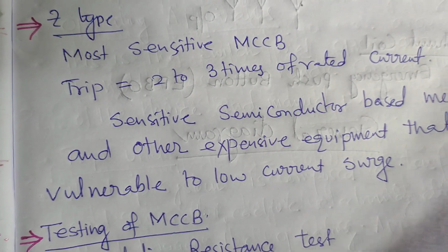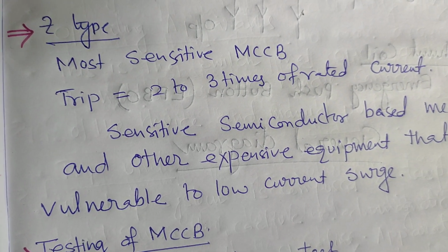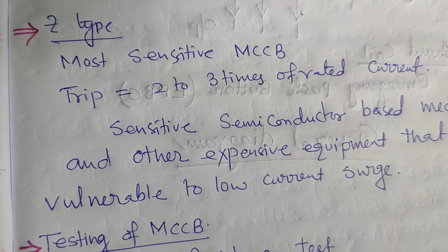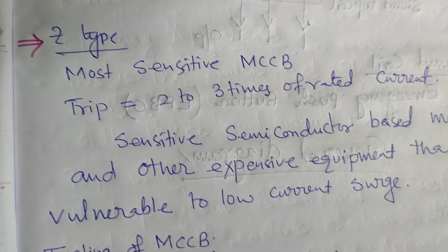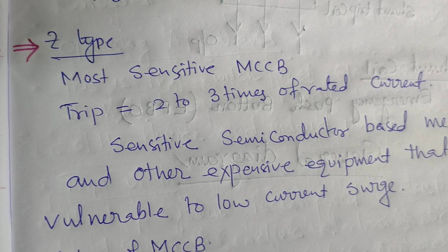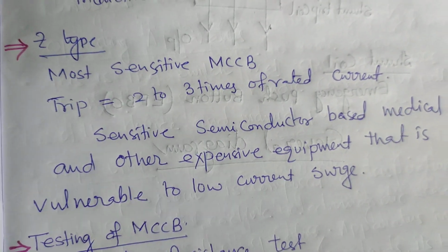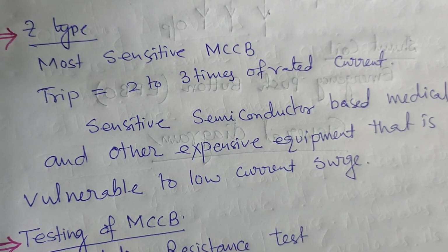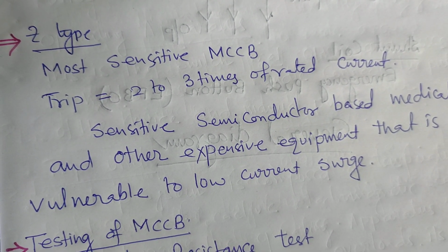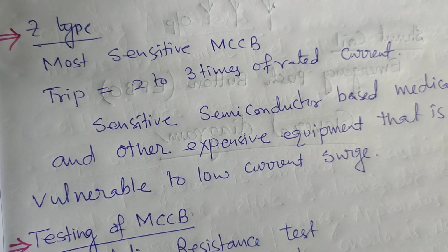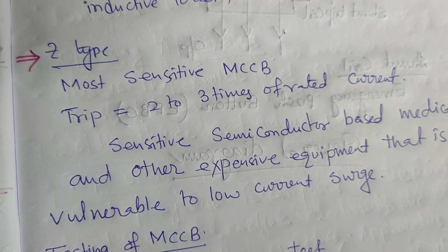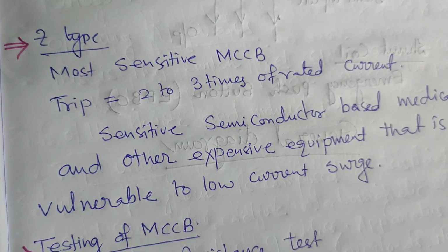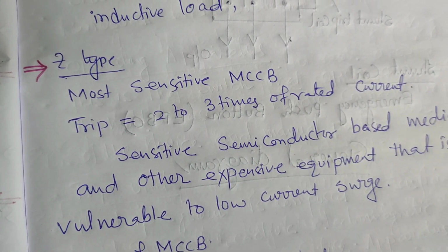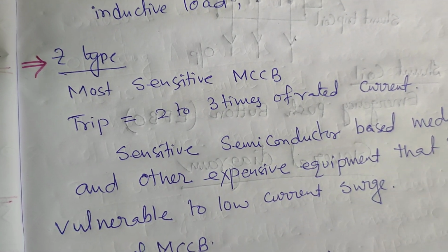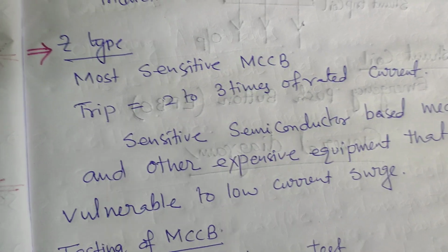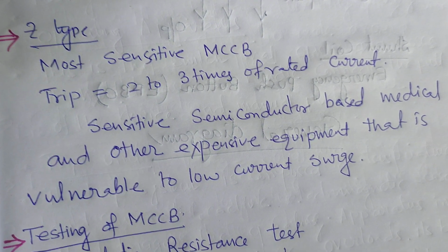Z type MCCB is the most sensitive MCCB. You have to remember that the most sensitive MCCB is the Z type. It trips at 2 to 3 times the rated current. This is used for medical purposes, medical apparatus, sensitive semiconductor-based medical equipment or other expensive equipment that is vulnerable to low current surges. If 2 to 3 times the rated current flows, the apparatus may be affected. So for these vulnerable machines we should use the Z type because it is very sensitive. If any such problem occurs, this MCCB will trip instantly, and the circuit will be saved without hazards and without fire hazards.